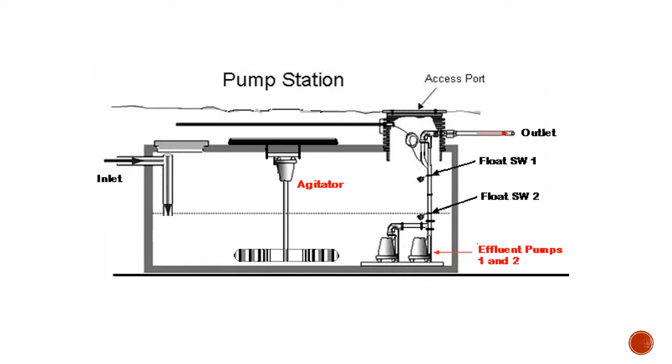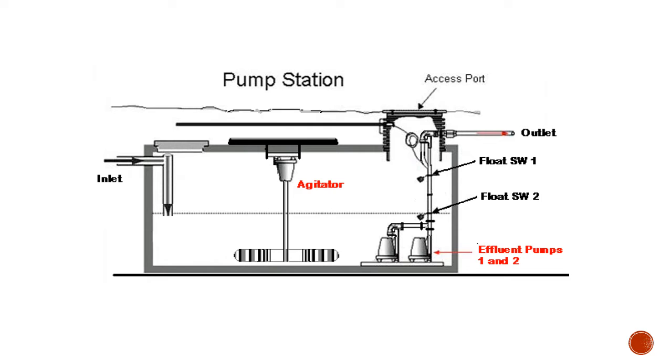A flip-flop circuit can be used in all kinds of places. The example I'm going to be looking at today is where we have a sewage or a wastewater lift station. Here as the water goes up and down I want to toggle between two different lift pumps. This greatly increases the lifespan of my pumps. And there's all kinds of other applications where you may want to toggle between two different outputs. So let's look at this particular application a little closer before we actually look at how to program it.